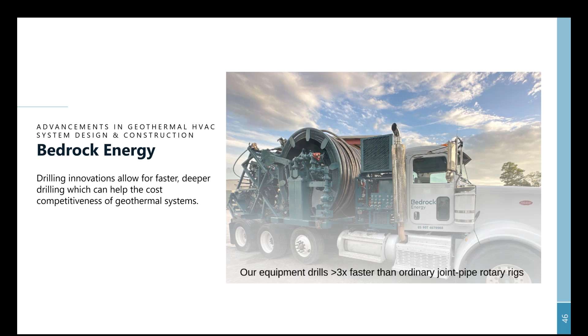I mentioned the testing we do on each site. Traditionally you'd have one test, maybe 1 or 2 boreholes, and design the entire geothermal field based on those test wells. But in a very large system you may have hundreds of boreholes, and how each one reacts can vary across wide areas. So real-time data from drilling each borehole allows for optimization of each borehole and of the system as a whole. You could be halfway through drilling and realize you're getting better performance than the testing suggested.